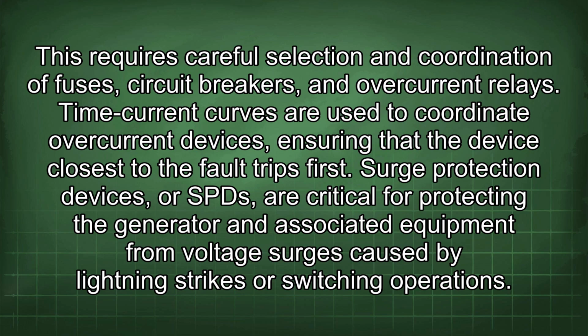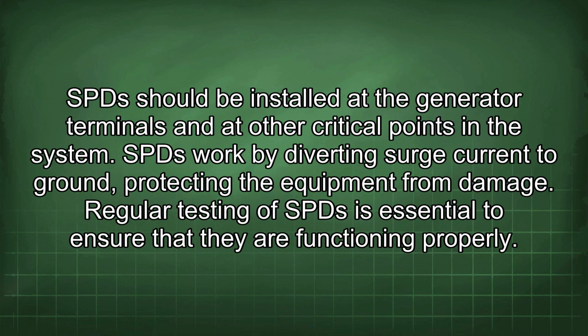Surge protection devices, or SPDs, are critical for protecting the generator and associated equipment from voltage surges caused by lightning strikes or switching operations. SPDs should be installed at the generator terminals and at other critical points in the system. SPDs work by diverting surge current to ground, protecting the equipment from damage. Regular testing of SPDs is essential to ensure that they are functioning properly.